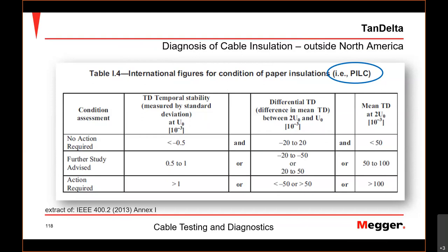On the other hand, you cannot do it the other way around, doing a long XLPE section with some paper in it, because the paper, like I say, is so dominant that you don't know, is it a bad paper section? Or is it a good, short paper section? Or is it something bad in the plastic? Little recommendation, if you happen to have any work on the cable, a fault or something, and you cut the cable anyway, go there, do a tan delta measurement, measure left, measure right. Maybe you can narrow it down that way. If you say, okay, from that point, in one direction we have only plastic, okay, measure it that way. And then you can at least see that section is good.